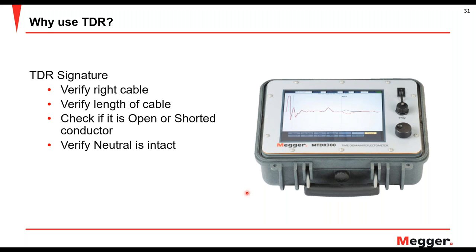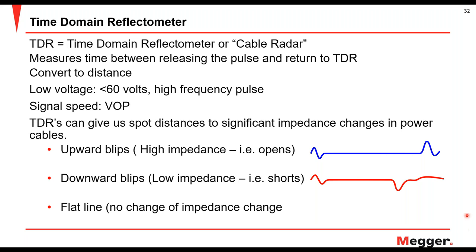As I was telling you before, a high end on the trace means there's an open. I have a red one that means I used arc reflection — the downward blip is where your fault is. If this were just a straight TDR shot in blue, the TDR is only about 60 volts but a high frequency pulse. It will flag where there is a short — this could be where your cable is actually grounded to the other transformer tank on a standoff, or where the center conductor and the shield are physically touching each other. No change means there's nothing — it's just flat.